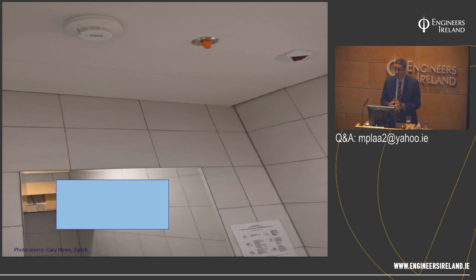Another common issue, anybody spot the mistake? Yeah, a few nods in the audience. The protective rubber cap is still on the frangible bulb. The system had been signed off by the installer as fit for purpose. And it comes down to the insurance fire protection engineer to walk around the building and find those. It's a bit embarrassing for the installer, but it shouldn't be something we find on site. It shows a lack of robust project management, sign-off and checking of the system. And there was more than one in that particular building. So, goes back to my previous point: if you'd relied on a piece of paper and not looked around the building, you wouldn't have found this.